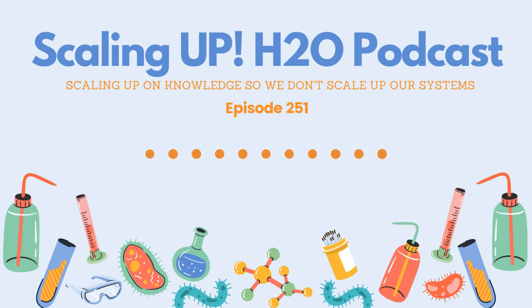I found one in my career where it was backwashing almost every 2 hours, way too much. By the way, when you backwash them too much, they're not as good as a filter. So if you have sand filters, and you should if you are dealing with cooling towers, make sure that you are working with the manufacturer of that filter so you understand how it works, how it needs to be set up. And now you've got a relationship with whomever is selling those devices. And when you have a problem, you can contact them, just like when they have a question about water treatment, they can contact you. Again, all these things, we haven't opened up our test kit yet.